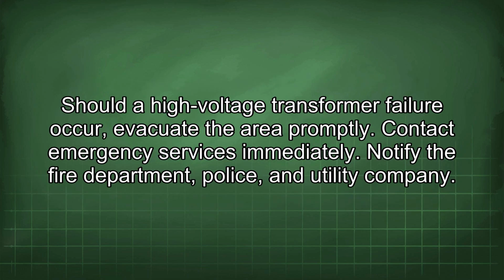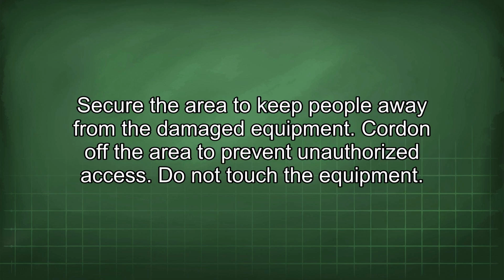Should a high-voltage transformer failure occur, evacuate the area promptly. Contact emergency services immediately. Notify the fire department, police, and utility company. Secure the area to keep people away from the damaged equipment. Cordon off the area to prevent unauthorized access. Do not touch the equipment.